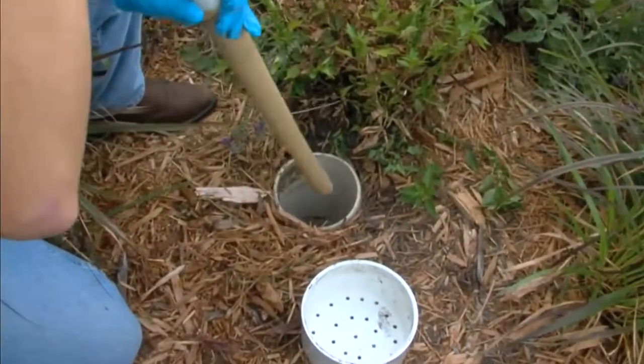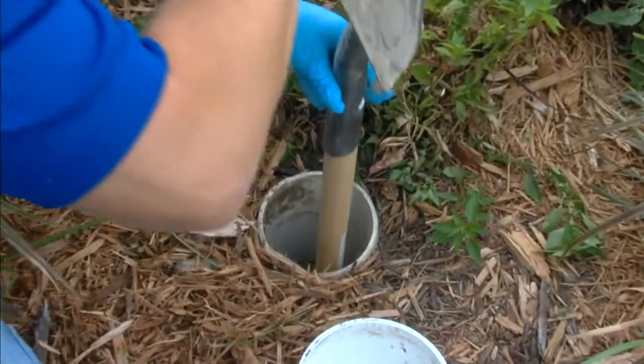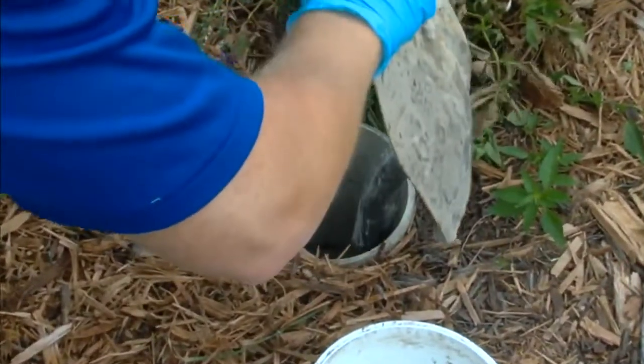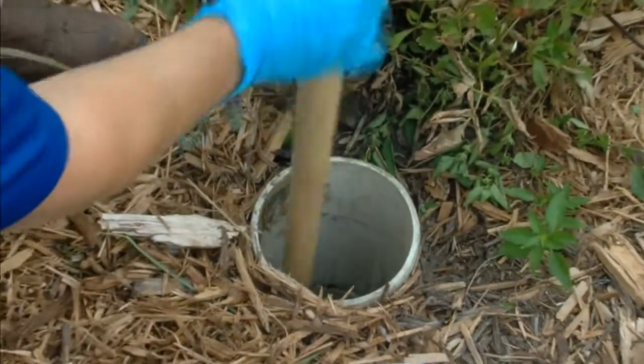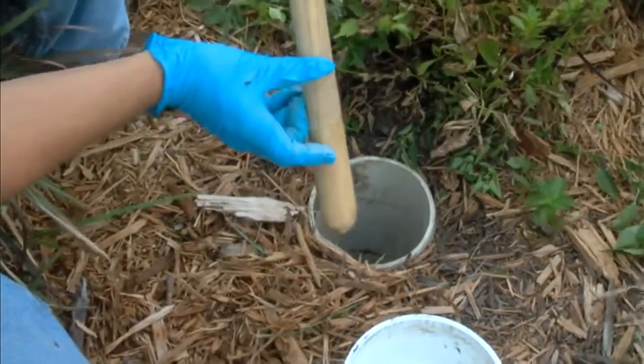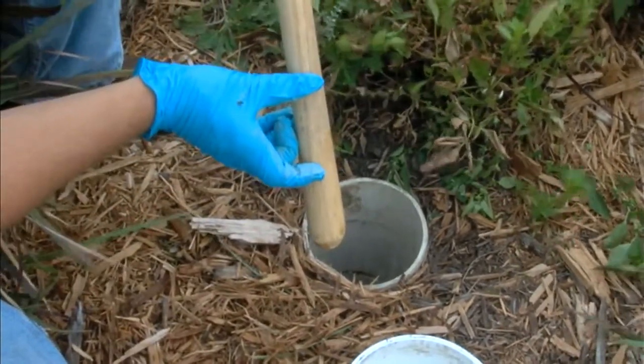Next, we're going to check the water level over top the media. So we take our dry stick, put it down the 6-inch port until we hit the media, bring it back up. We should have about 2.5 inches of water over top the media.